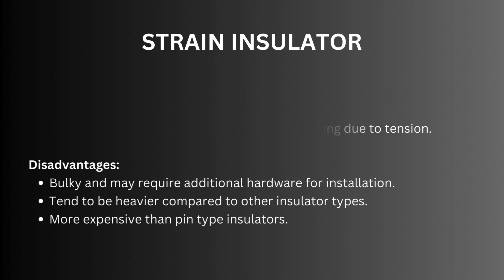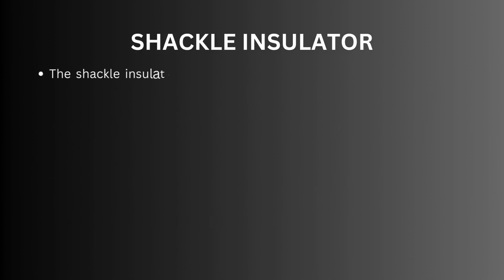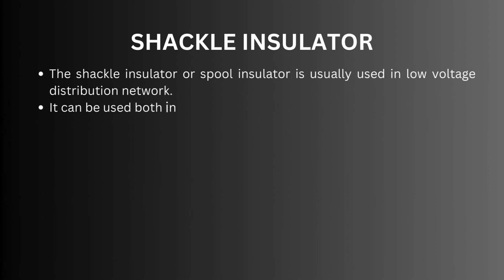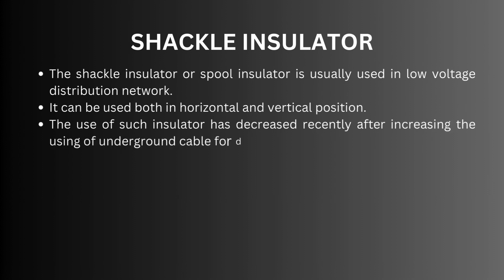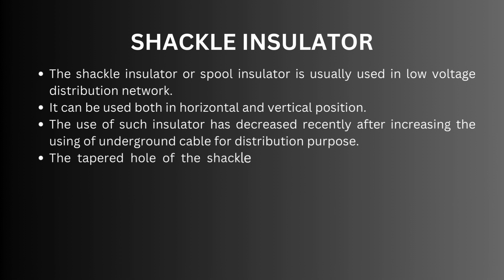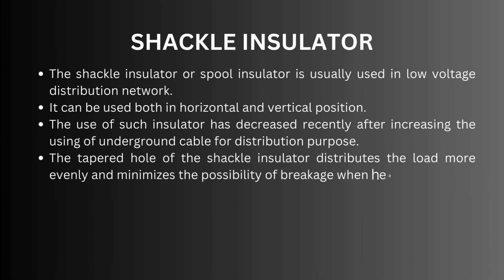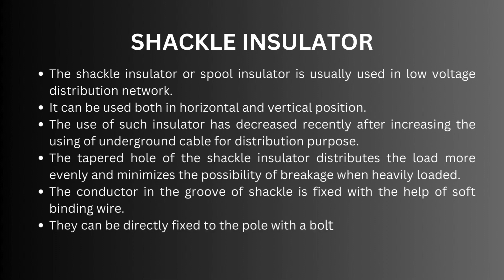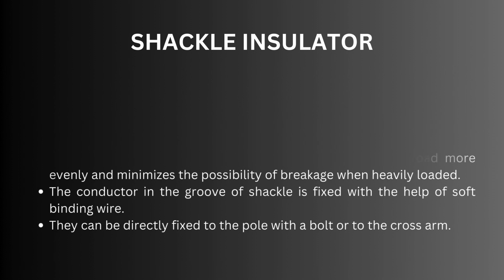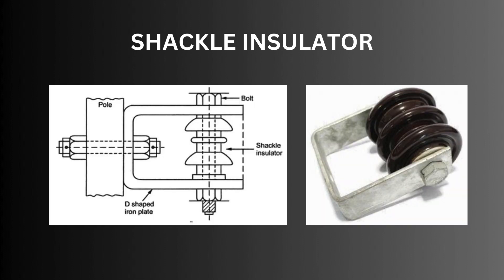Shackle insulator: the shackle insulator or spool insulator is usually used in low voltage distribution networks. It can be used both in horizontal and vertical positions. The use of such insulators has decreased recently due to increased use of underground cables for distribution. The tapered hole of the shackle insulator distributes the load more evenly and minimizes the possibility of breakage when heavily loaded. The conductor in the groove of the shackle is fixed with the help of soft binding wire, and they can be directly fixed to the pole with a bolt or to the cross arm. The figure illustrates a shackle type insulator.